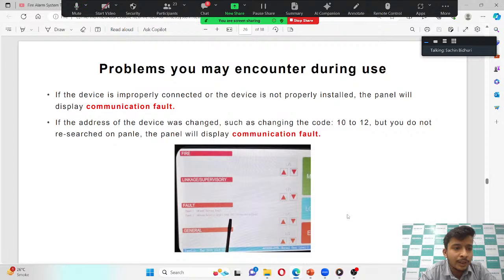If the address of the device was changed, such as changing the code 10 to 12, but you do not re-add it on the panel, the panel will display communication fault. What it means: suppose you have registered the device with the code 10, then you change the address of that device to 12 and you don't add this device again in the panel, then it will give a communication fault.